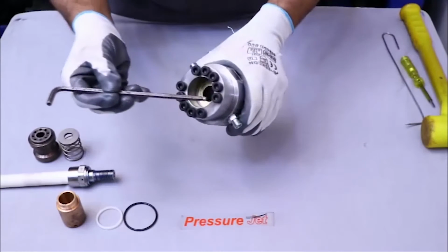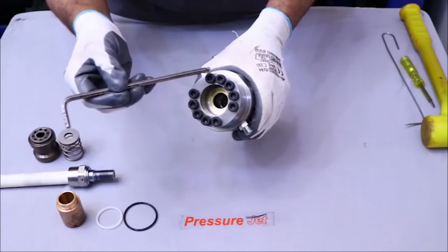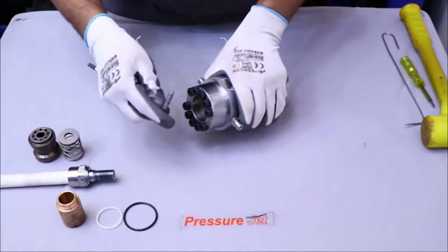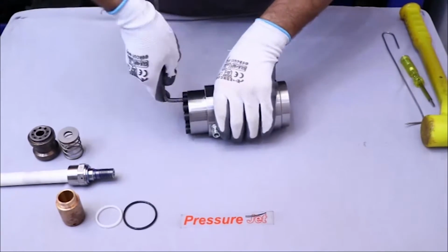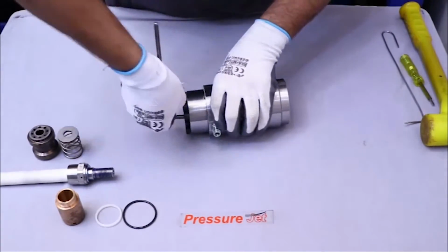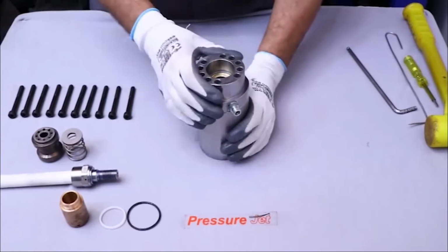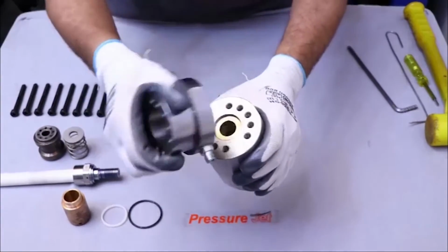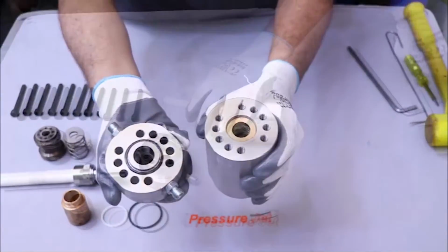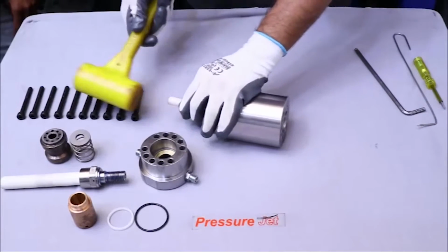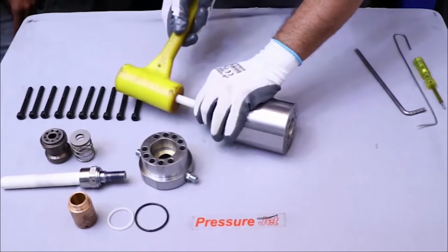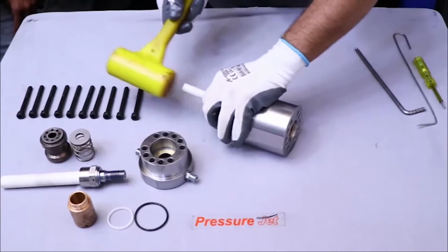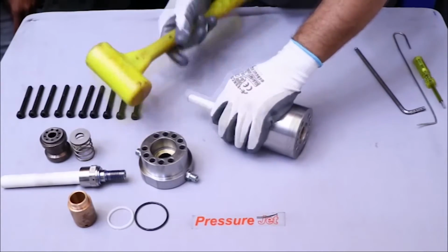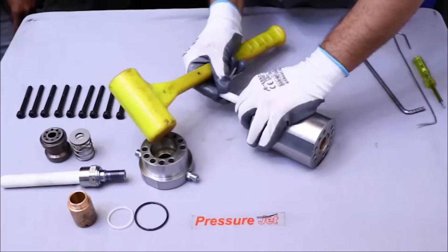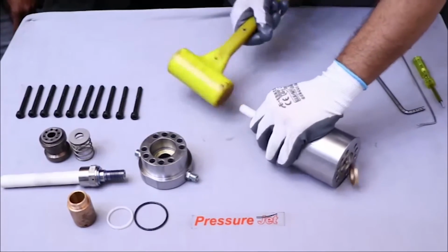Now using Allen key, remove 10 M8 cap screws from stuffing box. Separate stuffing box cover and stuffing box. Now push support ring from the opposite side using a nylon rod and rubber hammer. Remove support rings and plunger seal.